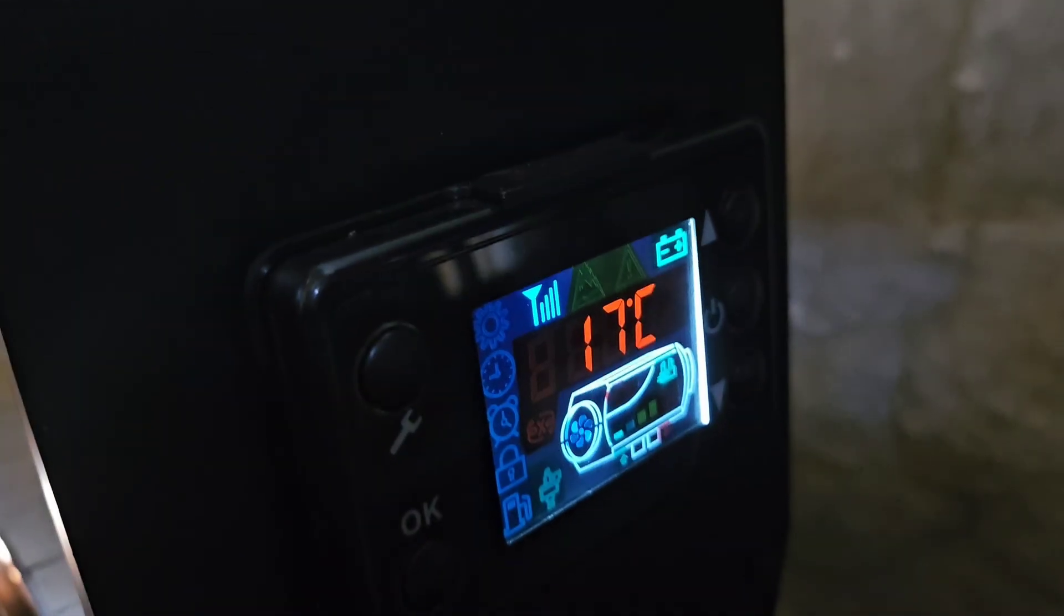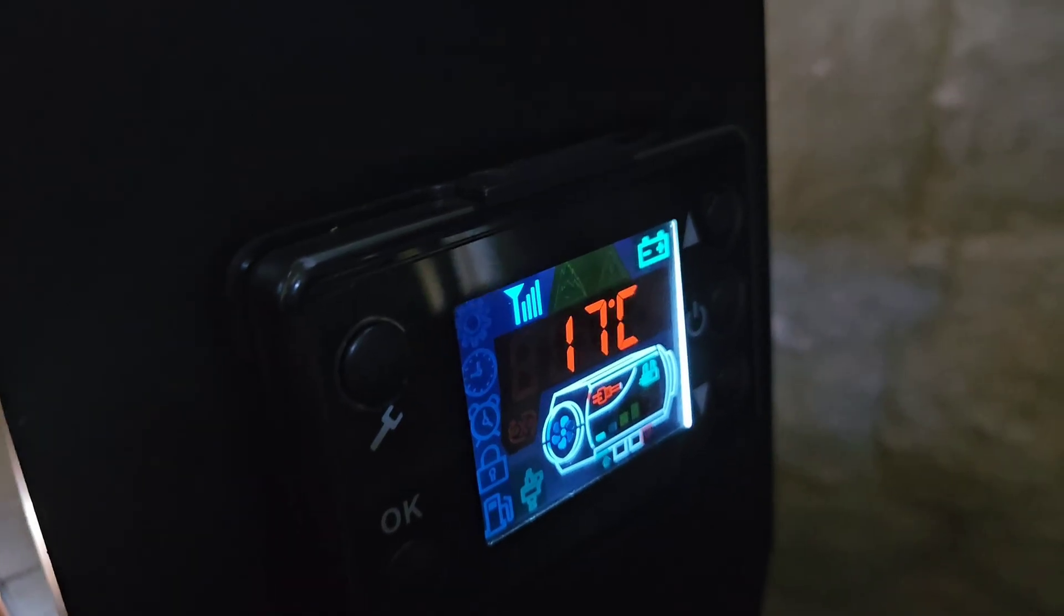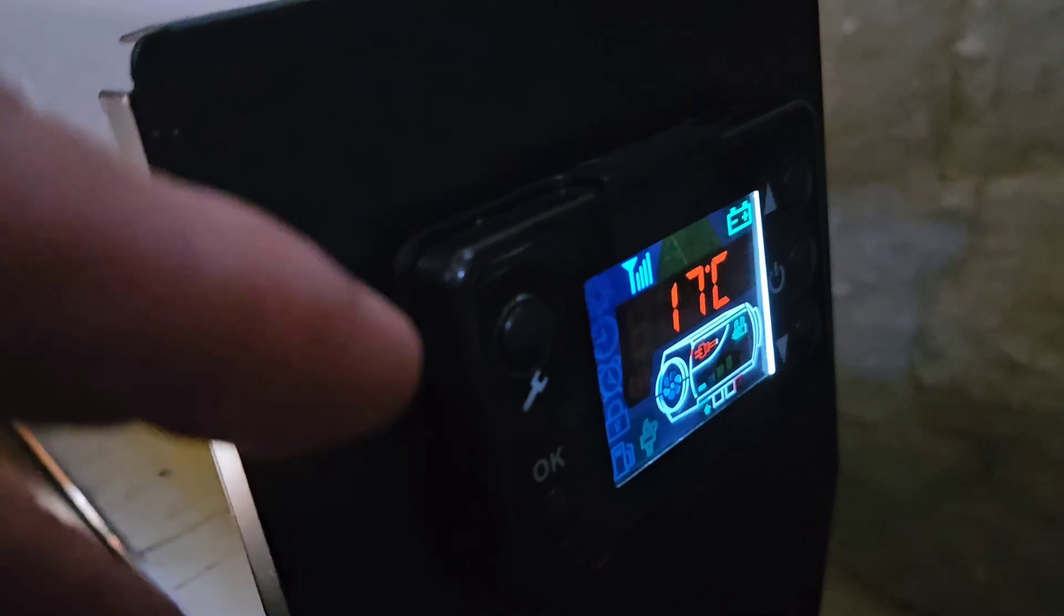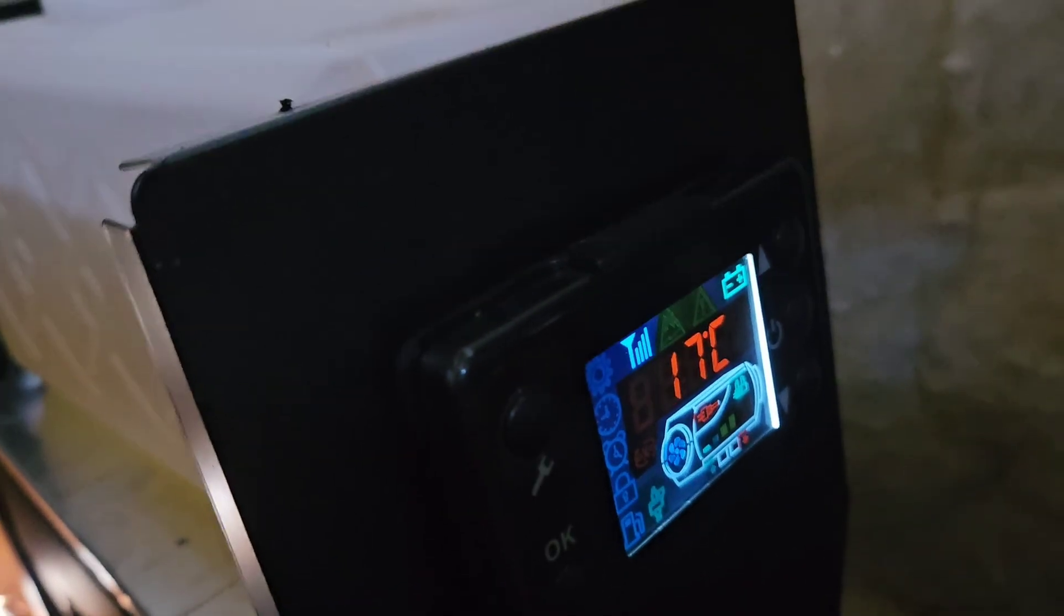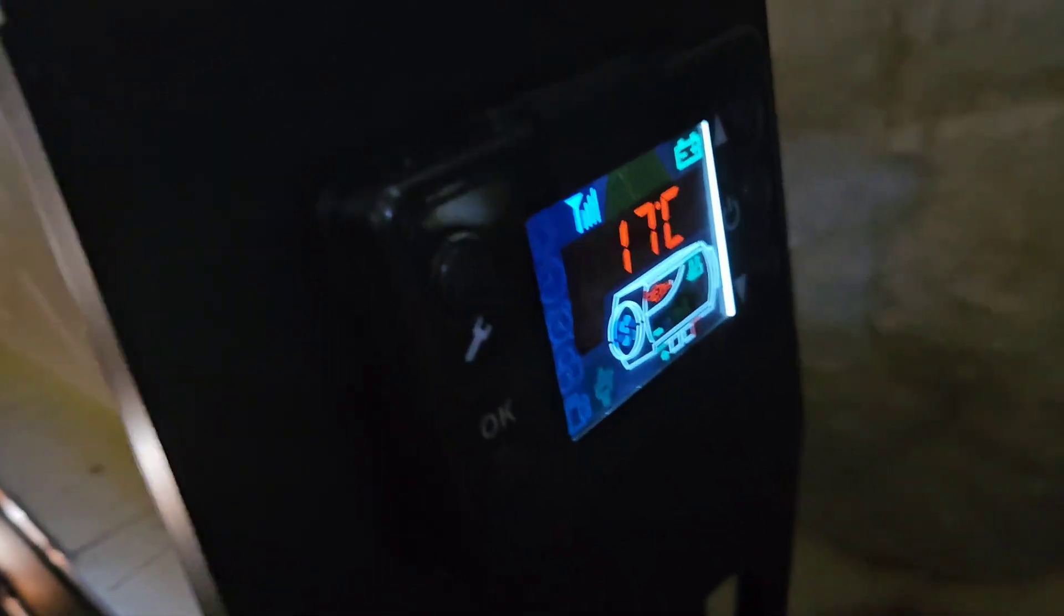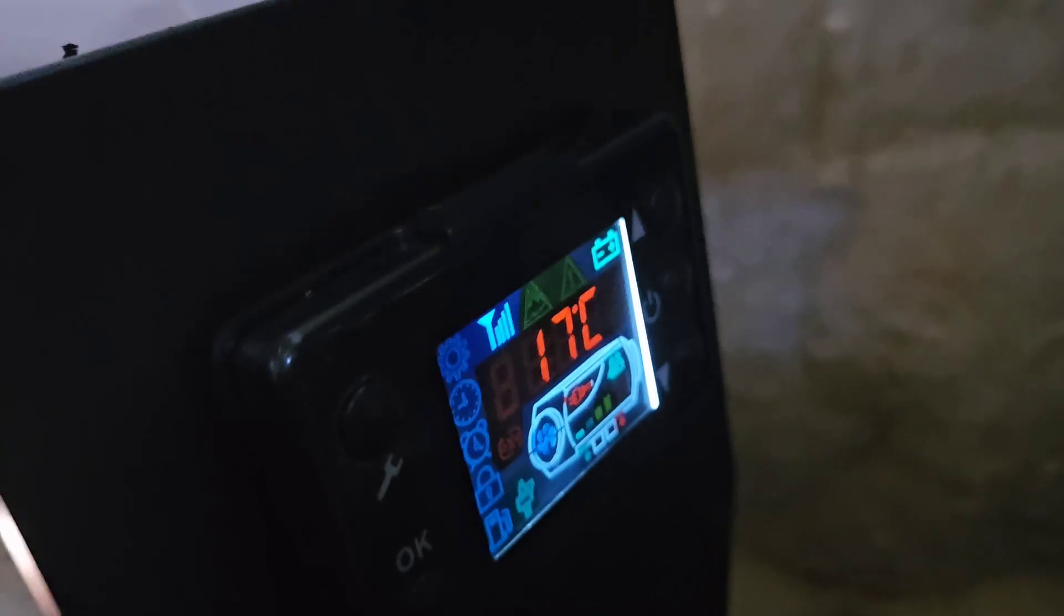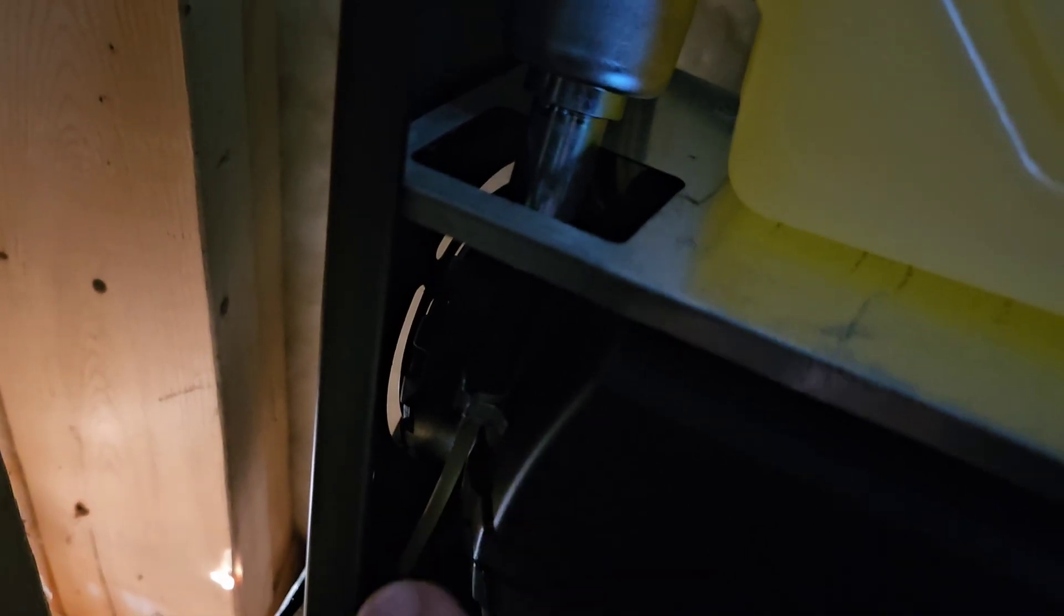We'll get it running. That's at least the start, so you at least know you're on the right track. If your voltage is wrong or something else is wrong, it'll throw up an error code immediately. I've had that happen—it's a pain. Like I said, documentation on these is horrible, it doesn't tell you what to do. But a problem you may come across is: this is the fuel tank, the actual heater is down there, and this is the fuel pump. Depending on the size of the fuel pump and how big your tank is...